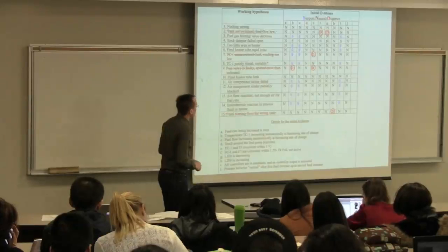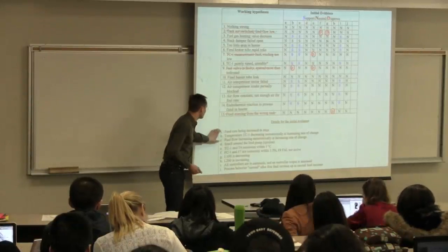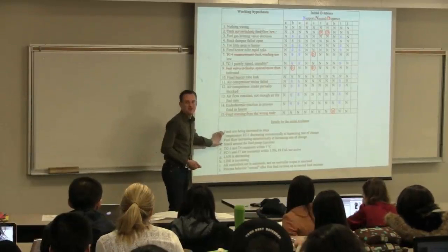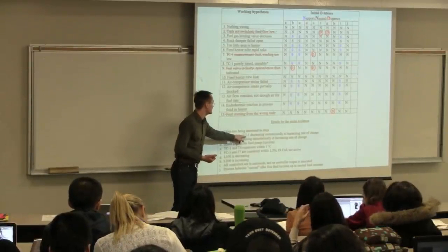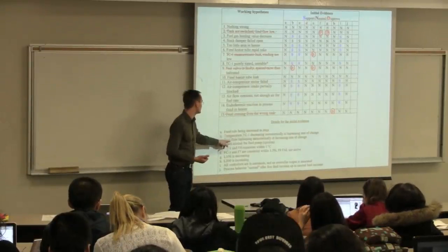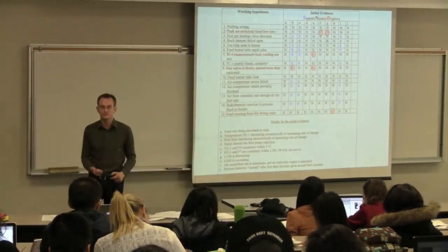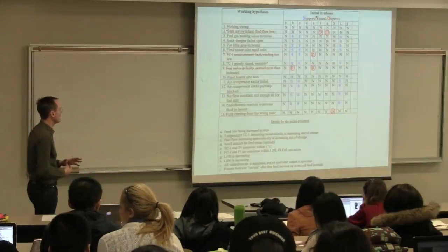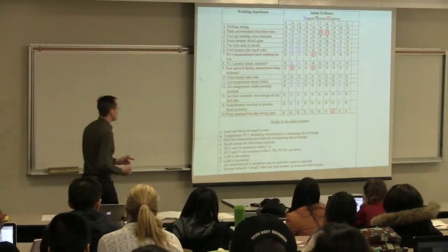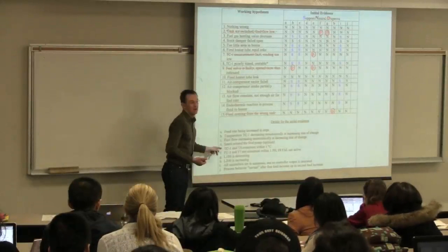What I prefer to do is to write down all the initial evidence that was given to me in the case study. The temperature is decreasing, so TC1 is decreasing. And the third piece of evidence I have is that my fuel flow rate is increasing. So those are three things that I read off those plots that were given. The fourth one here is that there was a smell around the fuel pump, and I can write there that that's actually an opinion.